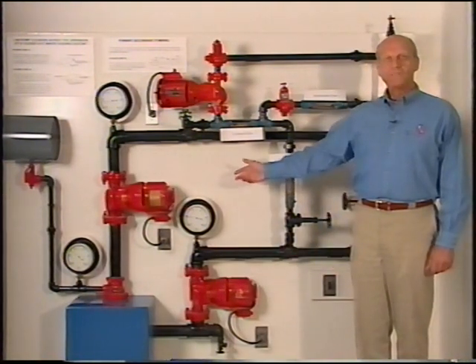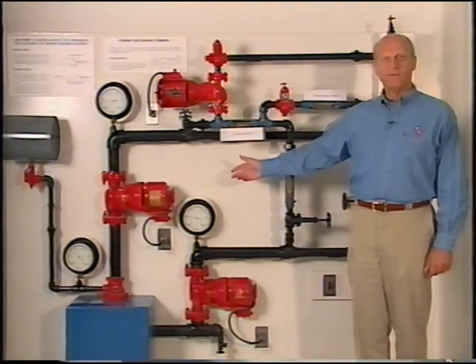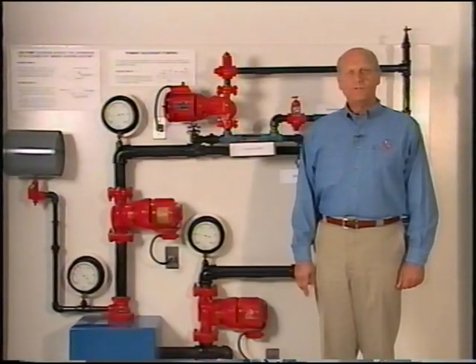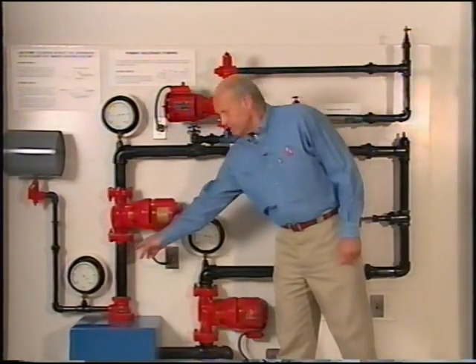This is our primary-secondary pumping demonstrator, designed to show how primary-secondary pumping actually works. To begin with, two pumping circuits can be isolated in the sense that pumping effects in one circuit will have no effect on flow in the other. Remember that the key point is to have low pressure drop in the piece of pipe that's common to both circuits. Here we have a primary circuit.